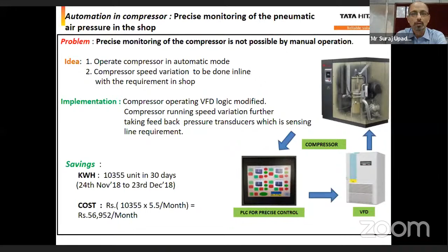So I would now show some examples of AI where we have inside. Our plant has 4 compressors, and each compressor is 1000 CFM. Now, all the compressors are installed with VFD logic, but we have installed one PLC precise control logic as well, which determines by looking at the consumption pattern how many compressors need to run. So in that way, compressors run at full load capacity always, and there is a saving of power.